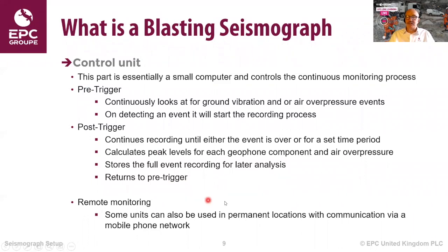It's worth noting that most seismographs these days can also be set up to work in a remote mode. So you can put them in a permanent location, a permanent installation, and communicate with them via the mobile phone network, or they may even report to an internet site.